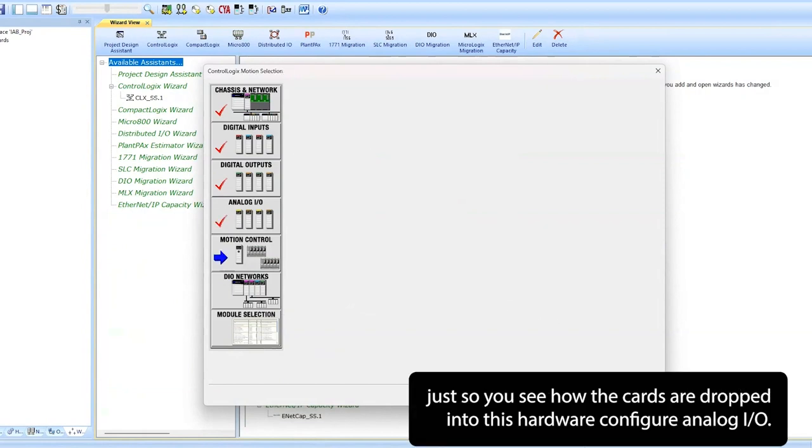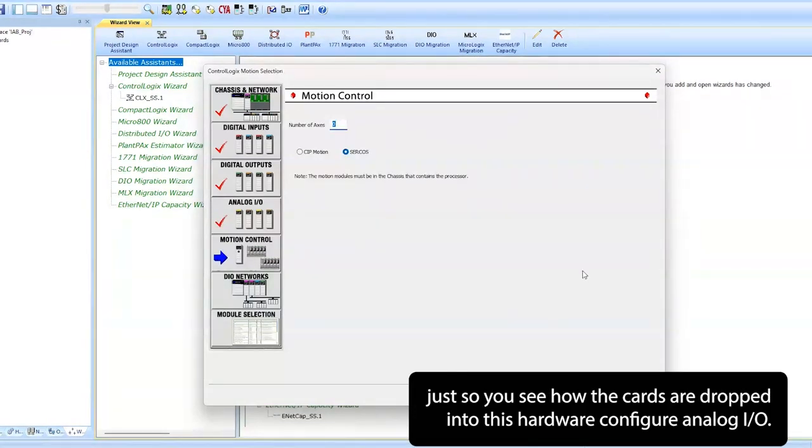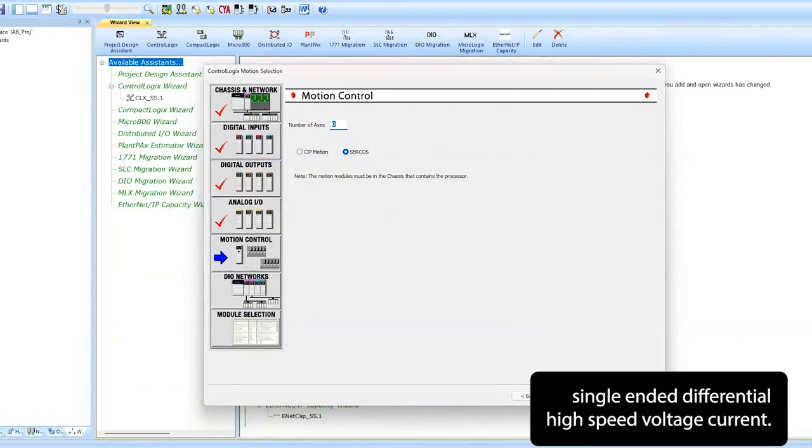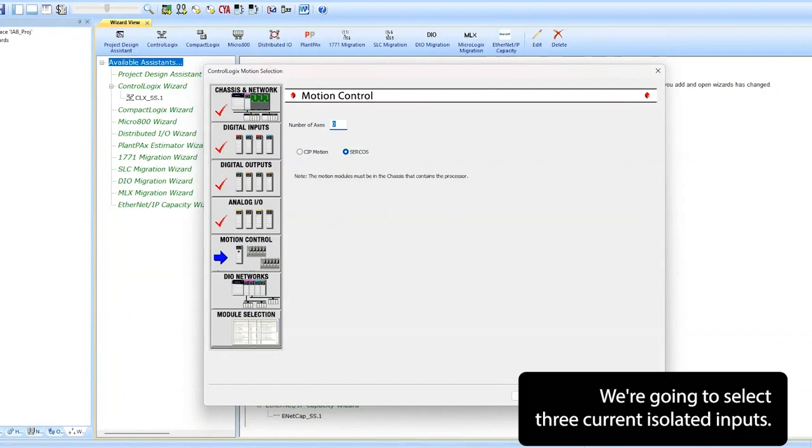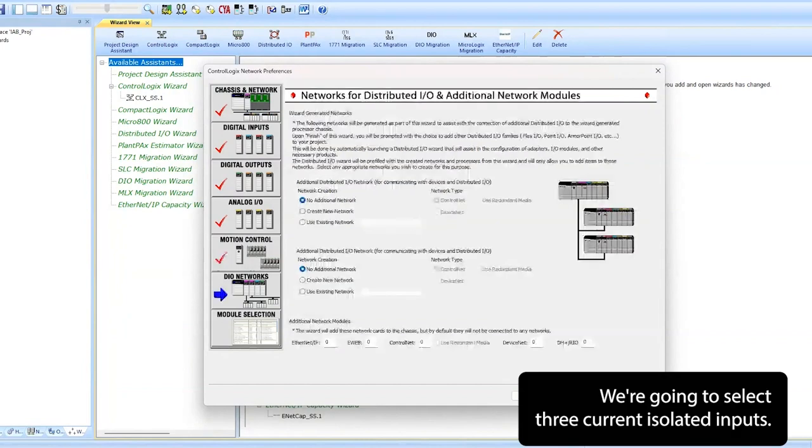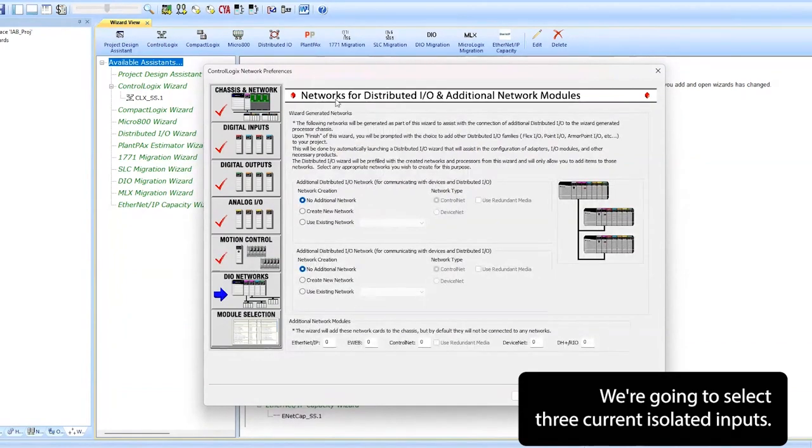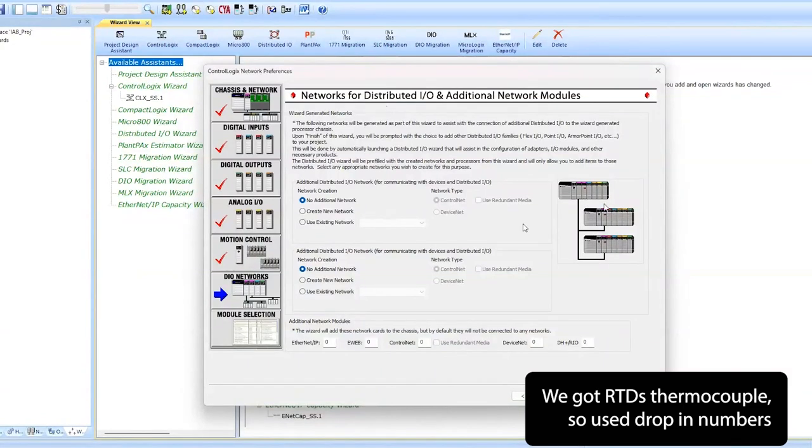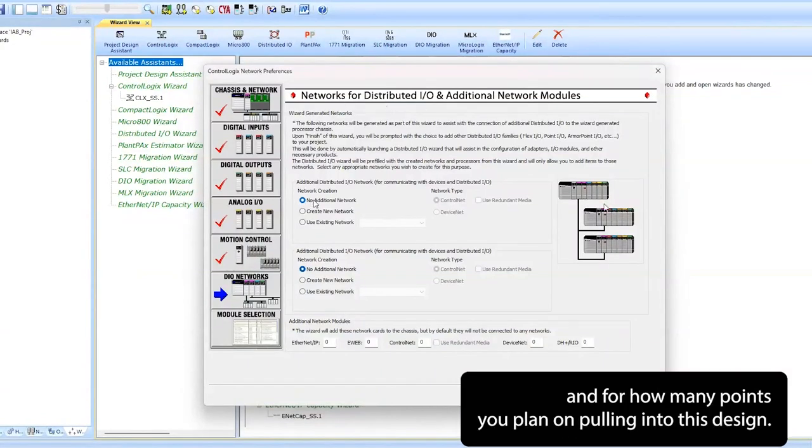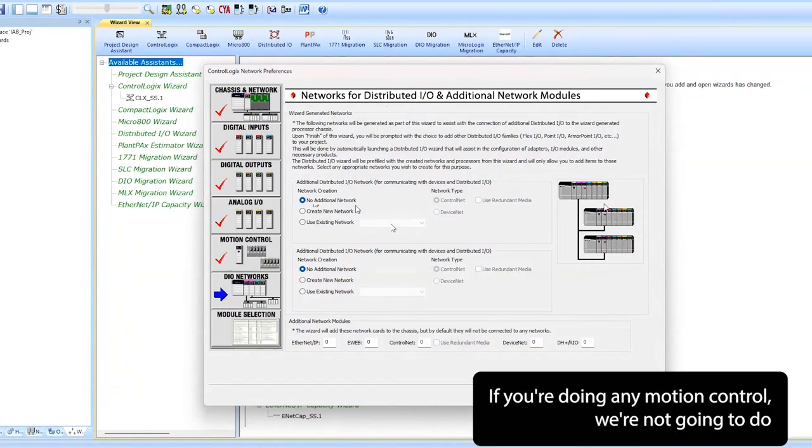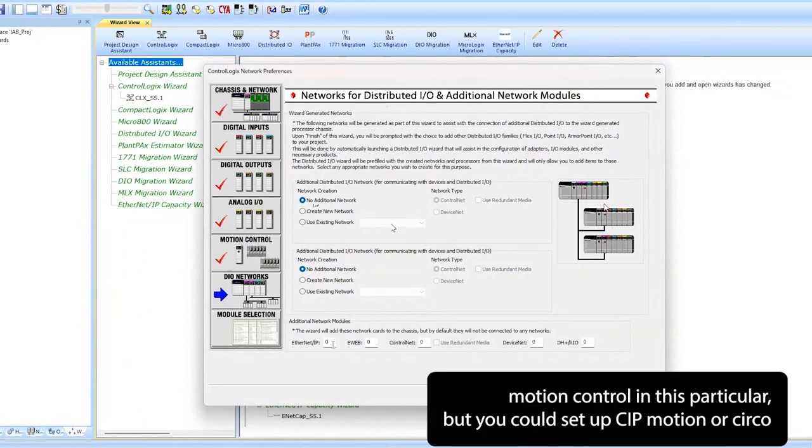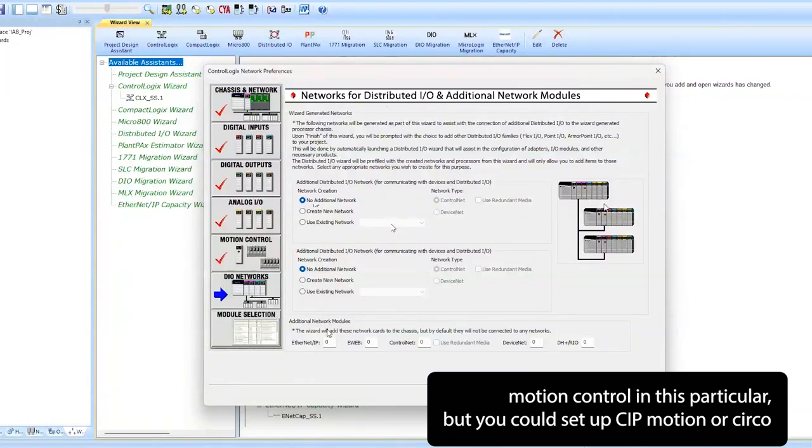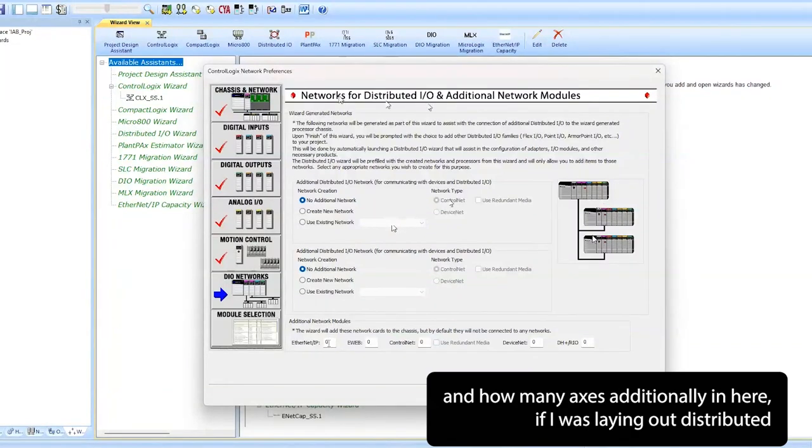Configuring analog I/O - single-ended, differential, high-speed voltage, current. We're going to select three current isolated inputs. We've got RTDs, thermocouples, so you're just dropping numbers in for how many points you're planning on pulling into this design. If you're doing any motion control, we're not going to do motion control in this particular example, but you could set up CIP motion or Sercos and how many axes.